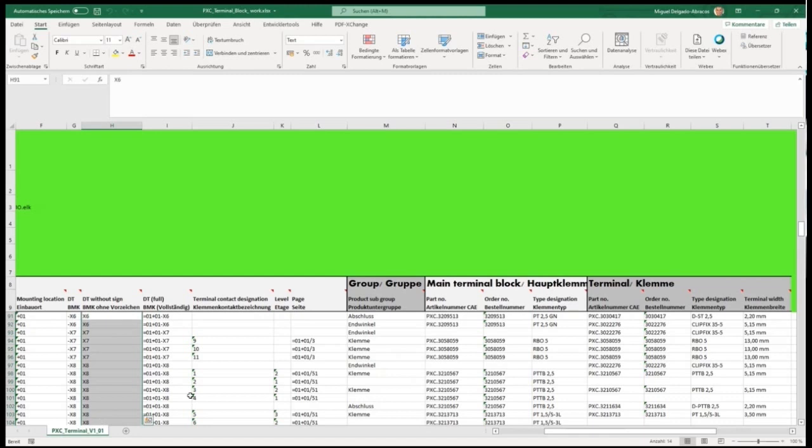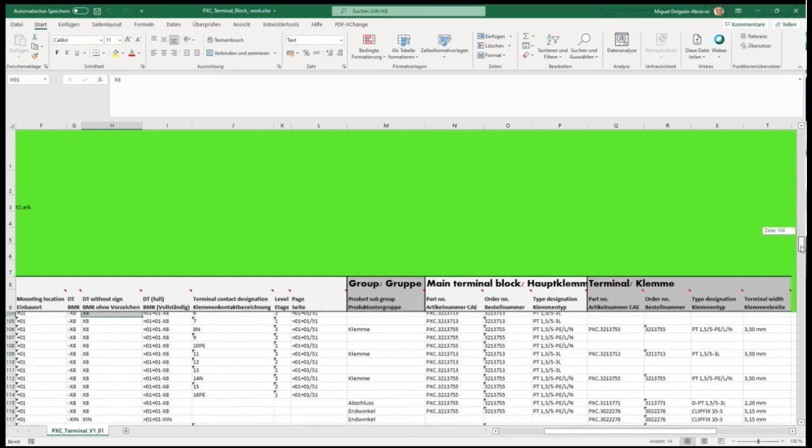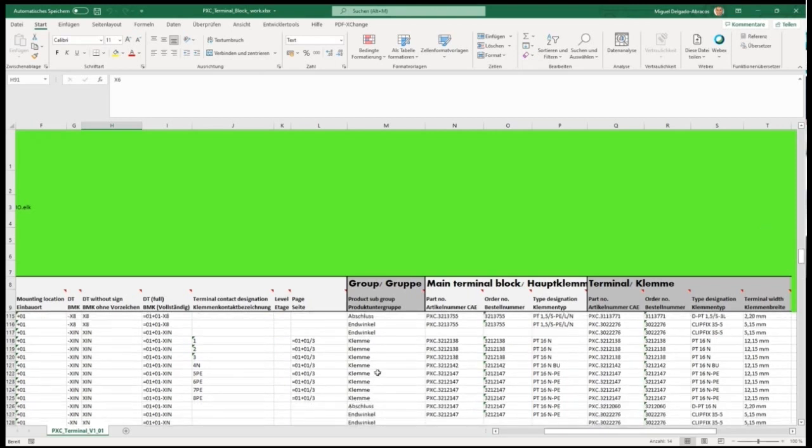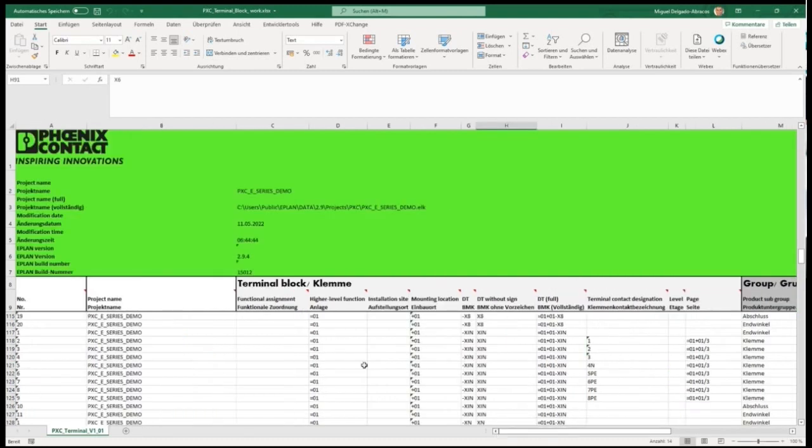So this is something where I would recommend to use planning. Really, if you want to export terminal marking, please export first to Project Complete Planning, and then you can see everything, how the terminal strip looks like. Then from this software you can export to marking, and then you have also the levels in the right order and so on. Because for the export of Eplan, just for double level terminal blocks or more level terminal blocks, it's easier to have it in planning, because with the sortation here, you can make a sortation, but the sortation doesn't fit then to the terminal strip. But if you want, you can have this export scheme and try it with your application to see if it works. If not, then I would recommend to really use planning.